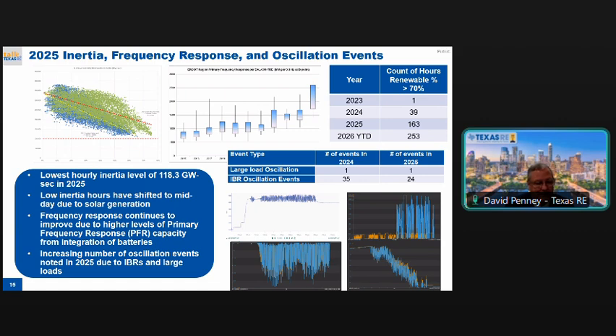So that trend is accelerating. One of the other interesting things related to inertia is we're seeing our lowest inertia hours are shifting. Historically, 3 or 4 years ago, our lowest inertia hours were at nighttime in March, 1 or 2 o'clock in the morning, under very high wind and very low load conditions. That's beginning to change. In 2025, for example, some of our lowest inertia hours are now in the middle of the day as we get more solar generation on the system. So even that is starting to change.